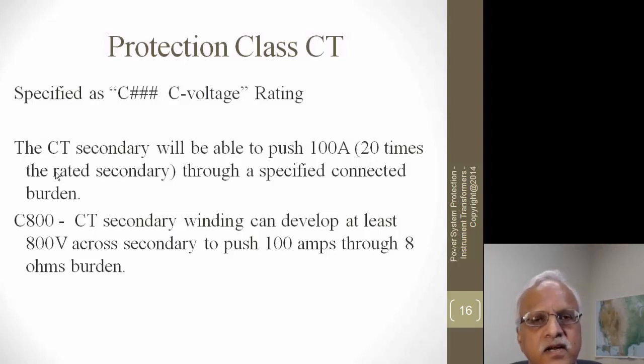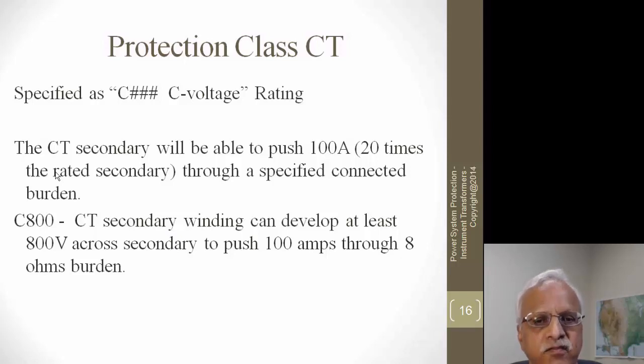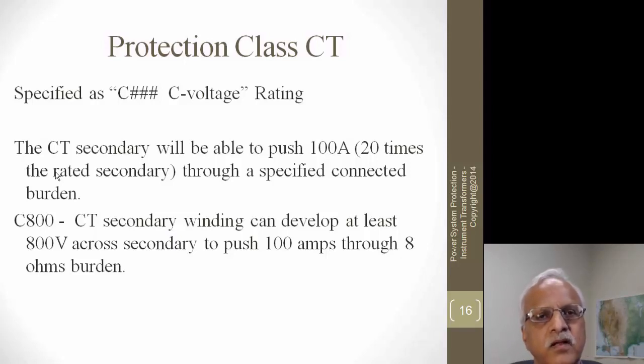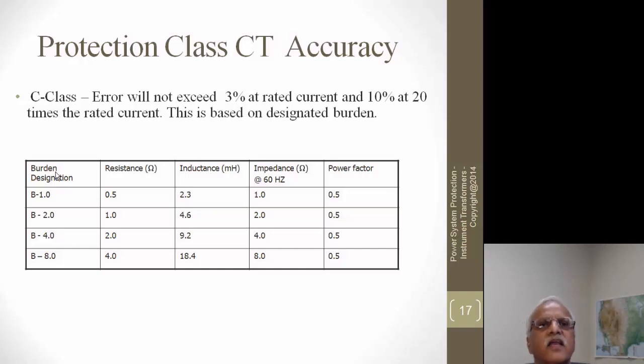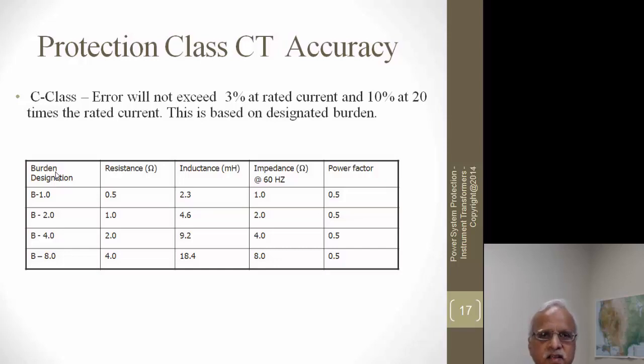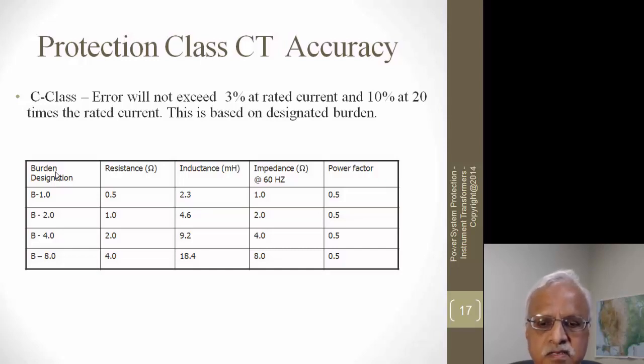C800 means the CT can develop 800 volts when 8 ohms is connected as a burden and 100 amps is flowing — so this CT is capable of developing 800 volts to push 100 amps through an 8-ohm burden. The burden for protection class is defined differently from metering: here the power factor is 0.5 rather than 0.9, meaning it is more inductive, reflecting the nature of relay coils.